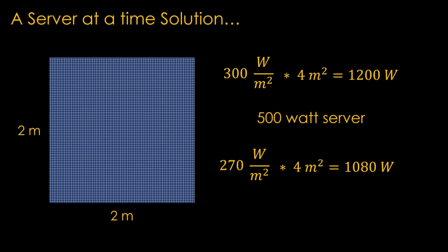This does give us an interesting benchmark for orbital data centers. We're inherently limited by the area it takes to generate power to run servers and radiate away excess heat, and the minimum area is on the order of 4 square meters per server.